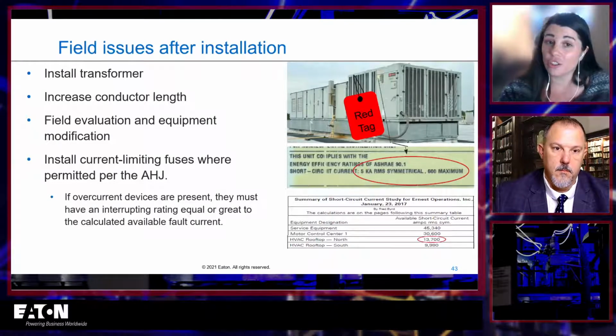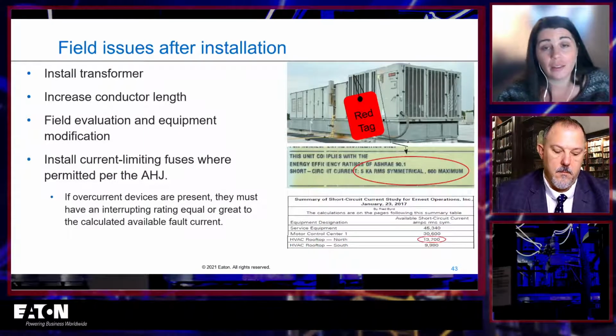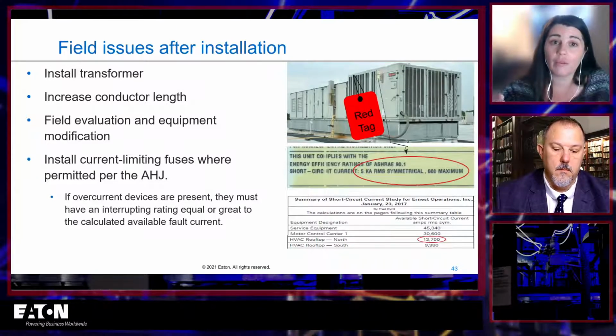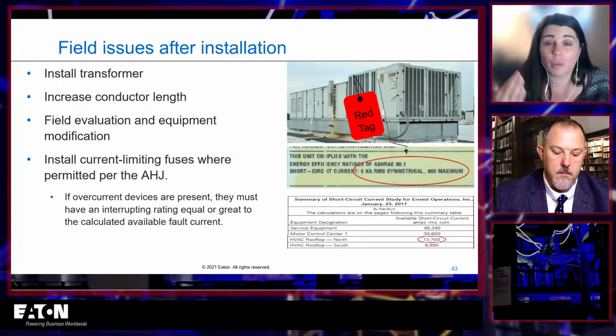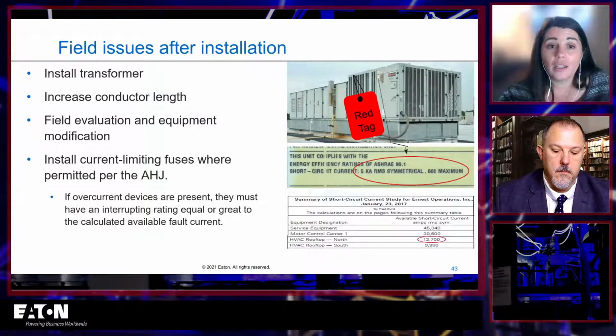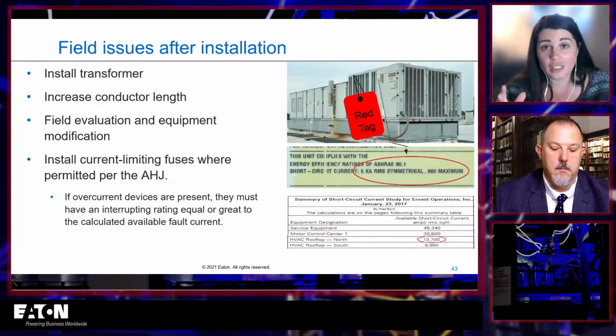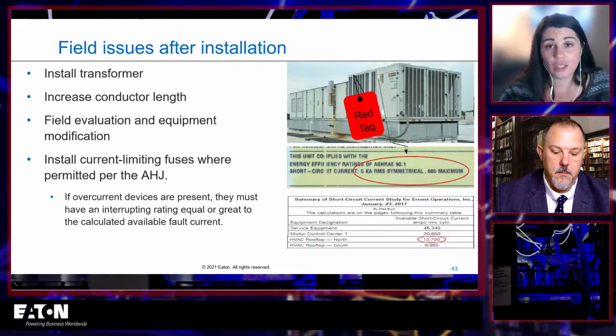The next thing is to increase the short circuit current rating. The best way to do this, in my opinion, is to get a nationally recognized testing laboratory out there, a third-party service, have them do a field modification of the equipment and relabel it with a new short circuit current rating. That is always the best solution. When it's the best solution, that also means it's probably the one that takes the most amount of time and is the most expensive. So I think it's probably not done as frequently. But from a true engineering standpoint, if I were to ever recommend a solution, that's the one I would always recommend. It's going to be the best guarantee for your system.